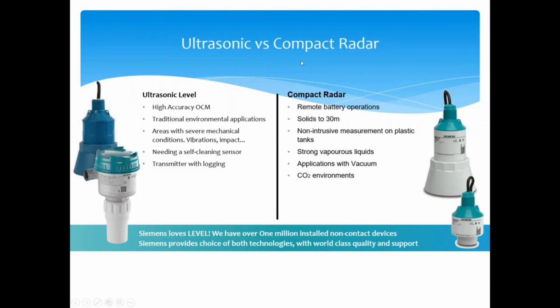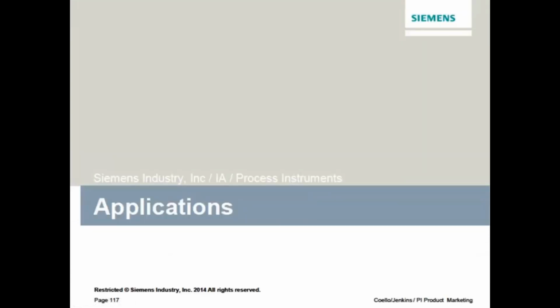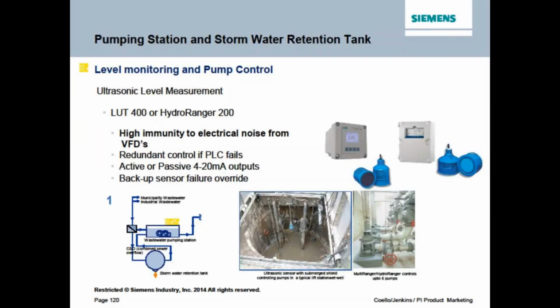Differences between ultrasonic and compact Bluetooth radar. I'll just point out the radar here. Really good for remote battery operations. Your range can be as high as 30 meters, which is longer than we'll go with ultrasonics. And you can measure through plastic tanks, great with vapors in your headspace, can work in a vacuum or carbon dioxide environments. So now the last 15 or so slides, I just run real quick through a bunch of applications and talk about which would make more sense between ultrasonic and radar.